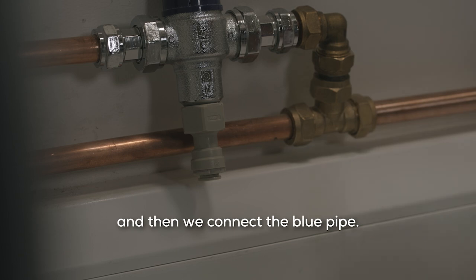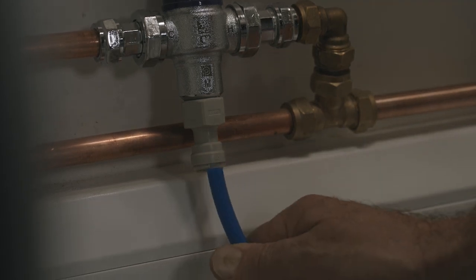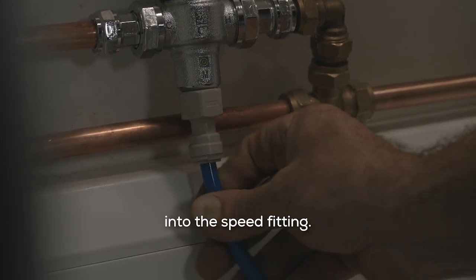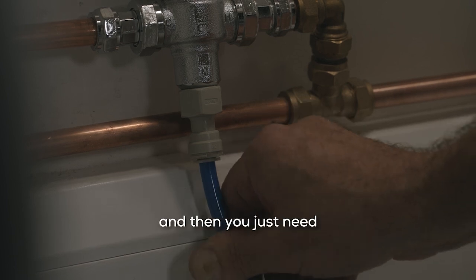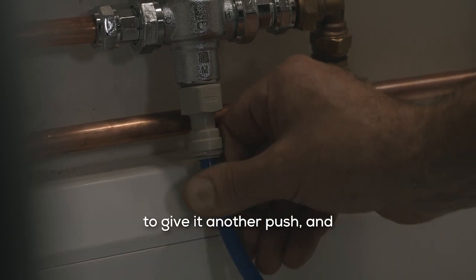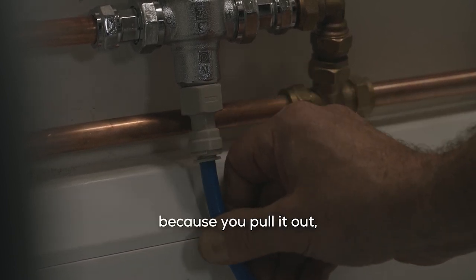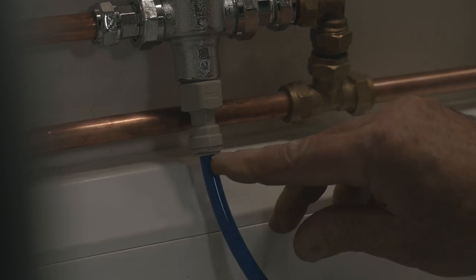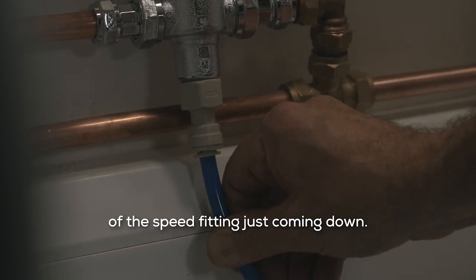And then we connect the blue pipe in there once again. You push the blue pipe into the speed fitting, you'll feel it go in, and then you just need to give it another push and you'll see that it's locked because you pull it out and you can see the collar of the speed fitting just coming down.